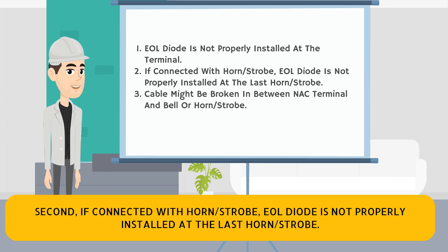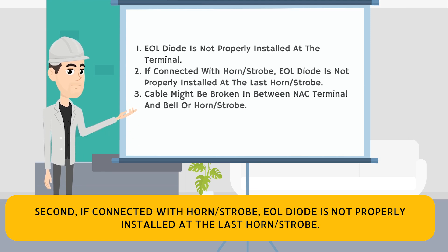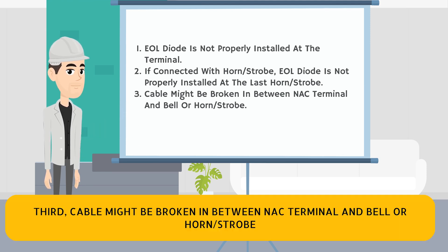Second, if connected with a horn strobe, the EOL diode is not properly installed at the last horn strobe. Third, the cable might be broken in between the NAC terminal and the bell or horn strobe.